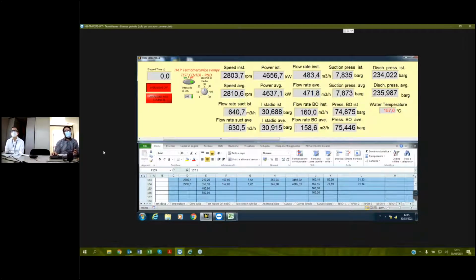So we have the direct reading of the absorbed power by the whole train. We have the flow rate at the discharge flange and the flow rate at the bleed off flange. This machine is composed of 10 stages, but at the end of the third one we have a bleed off line, and so we measure the flow rate with a flow meter. And we have all the pressures: suction pressure, discharge pressure, the bleed off pressure, and also the pressure at the end of the first stage. This measurement is very important in the definition of the NPSH 3%. On top of that, we have the reading of the vibration and the noise.